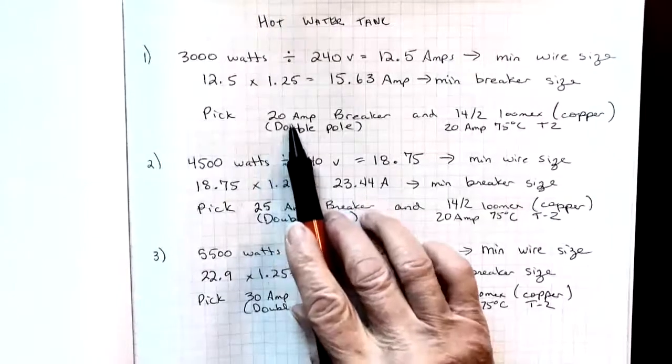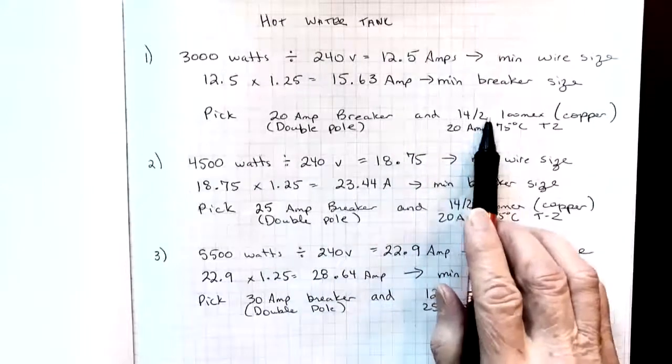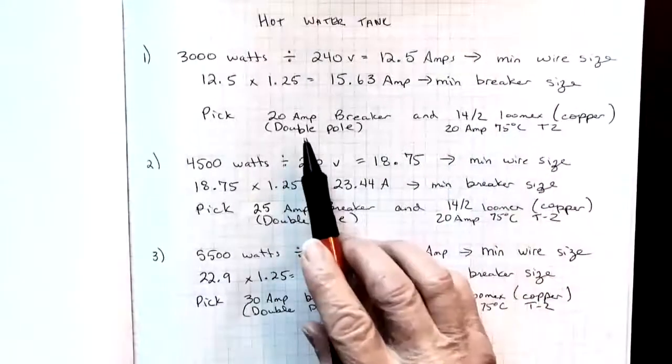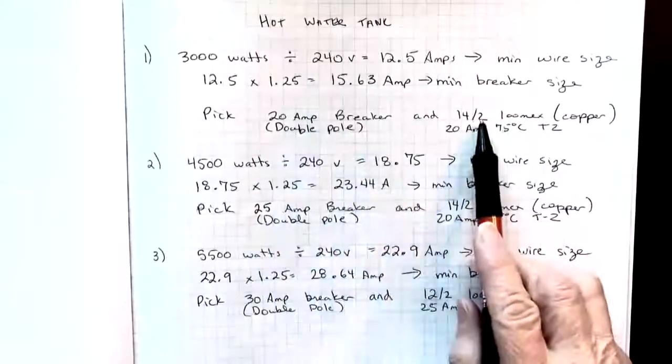So we pick a 20 amp breaker and the 14/2 Loomex when we're using copper. It's a double pole breaker because of the 240 volts.